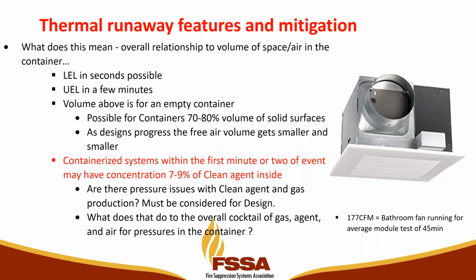Consider the volume for a container - how much free space do you have, and not just free space, but what's in the way relative to your failure modes? Do you have deflagration vents or doors that will open? Do you have shrapnel risk if it's not an open access area? More and more of these containers are getting denser, so there's very little free space inside. One question, not my area of expertise, is that if you put in a clean agent, it increases the pressure inside the container a bit - what design considerations do you need for an off-gassing event so the air pressure is dealt with appropriately?